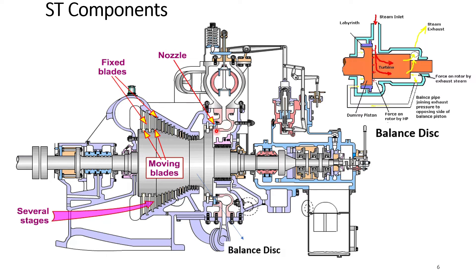Here is the nozzle through which the steam goes inside the turbine. This is the balance disc. The purpose of the balance disc is to balance the thrust of the turbine, because when steam is flowing through the turbine the pressure is higher on the inlet side and lower on the outlet side. So the shaft tries to shift towards the outlet side, but the steam acting on this collar tries to push the rotor back towards the inlet side. That is how it achieves balanced thrust, and this residual thrust is balanced in the thrust bearing.